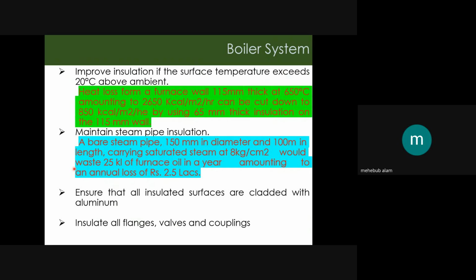In the boiler system, some other parameters are like improving insulation. We have to improve the insulation system to reduce the heat loss in the surface wall of the boiler, like the heat loss from a furnace wall of 115 millimeter thickness at 650 degrees centigrade, amounting to 2650 kcal per meter square per hour, can be cut down to 850 kcal per meter square per hour.